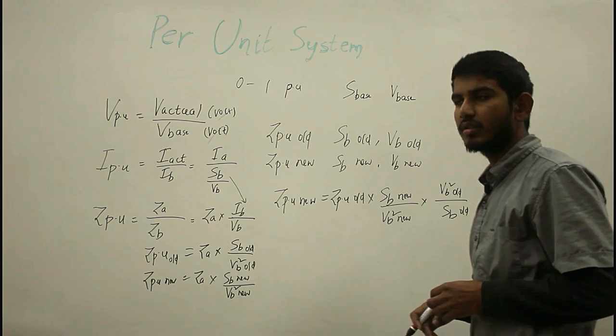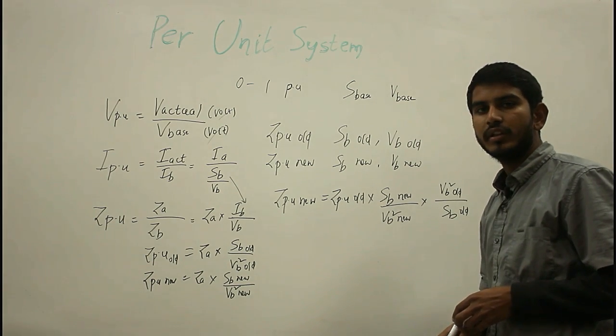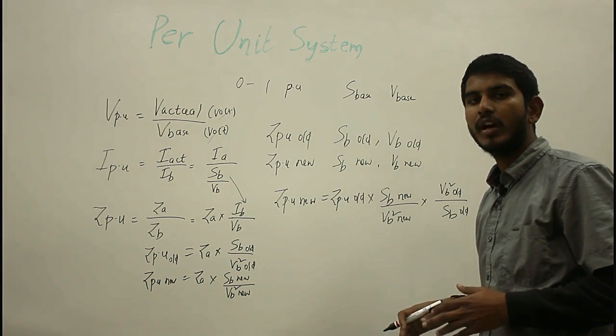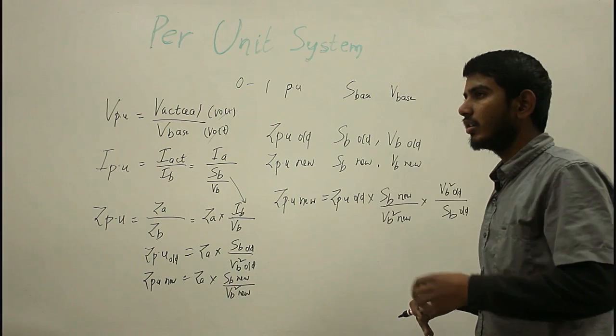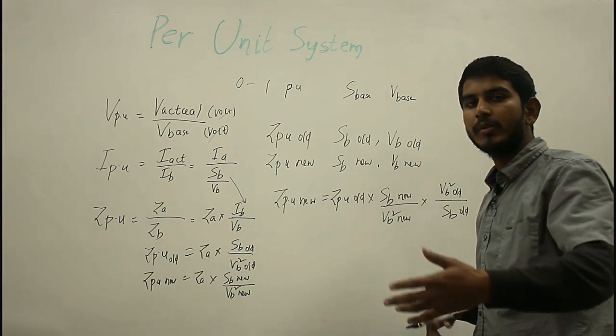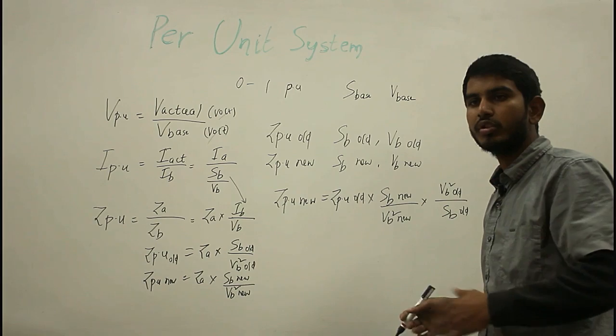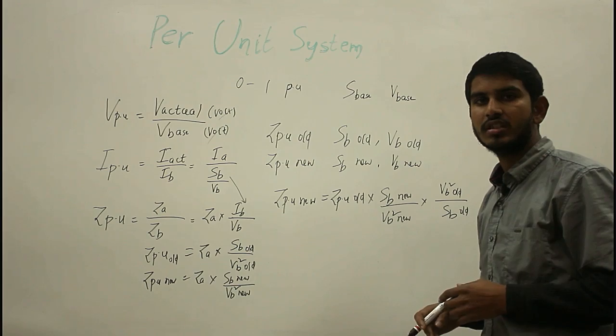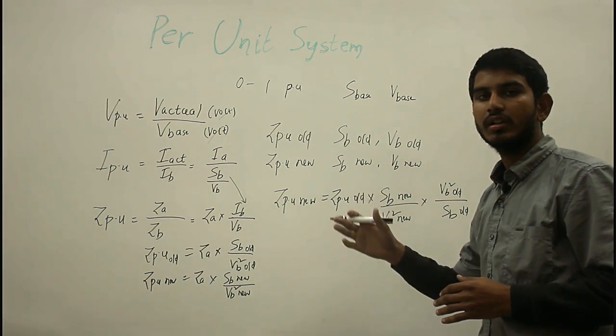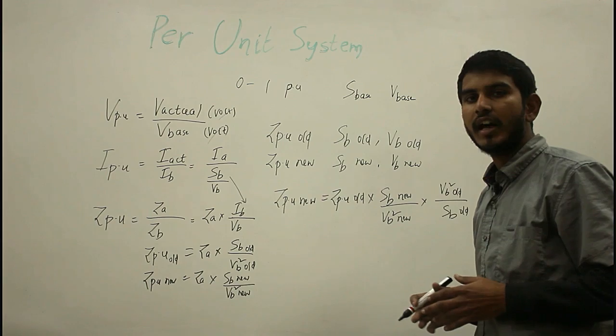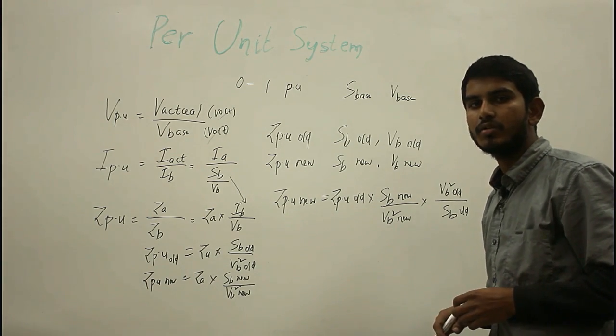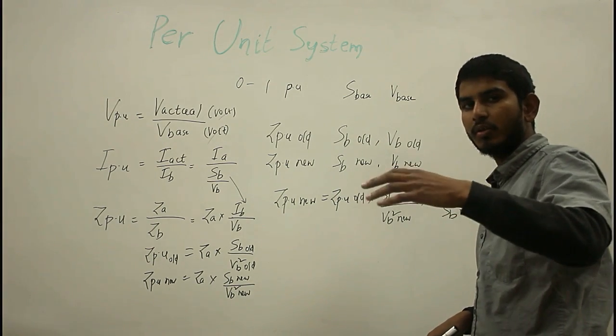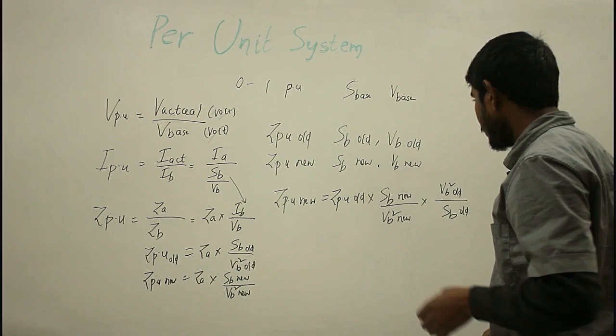The advantage of the per-unit system is that an electrical quantity — whether voltage, current, or impedance — when referred from one side of a transformer to the other, there is no change in the per-unit values. That means Z per unit referred to the primary side equals Z per unit referred to the secondary side. This is a great advantage of the per-unit system. Additionally, the values of parameters or electrical quantities fall within a narrow range compared to their actual values.